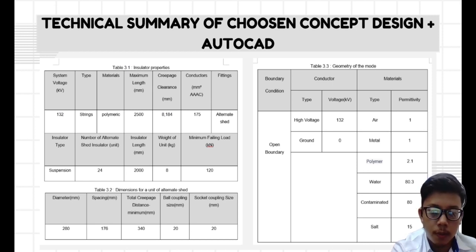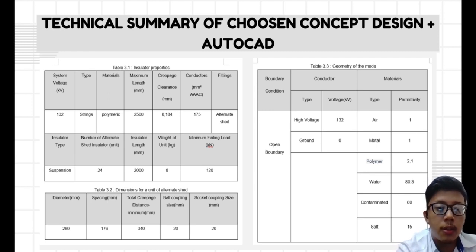Okay, next, for the insulator properties, the system voltage that we are using is 132 kV, the type is strings, the material is polymeric, the maximum length is 2500 mm, the creepage clearance is 8,184 mm, the conductors are 175, the fitting is alternate shed, the insulator type we are using is suspension, the number of alternate sheets for our suspension insulator is 24. The insulator's length that we designed is 2000 mm, the weight of the insulator is 8 kg, and the minimum failing load is 132 kN.